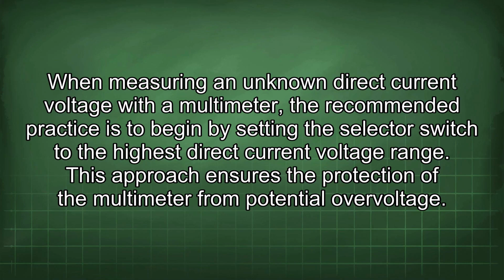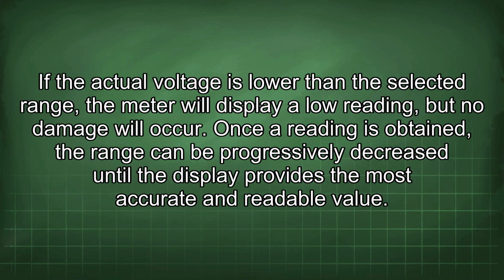When measuring an unknown direct current voltage with a multimeter, the recommended practice is to begin by setting the selector switch to the highest direct current voltage range. This approach ensures the protection of the multimeter from potential overvoltage. If the actual voltage is lower than the selected range, the meter will display a low reading, but no damage will occur.